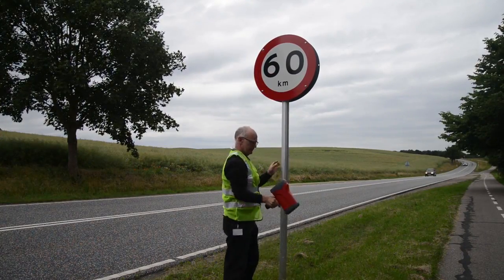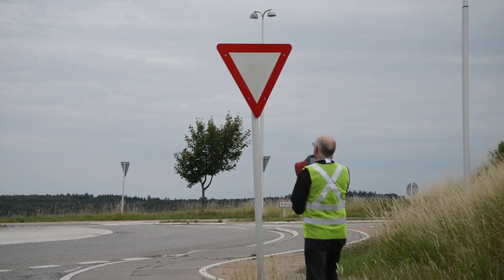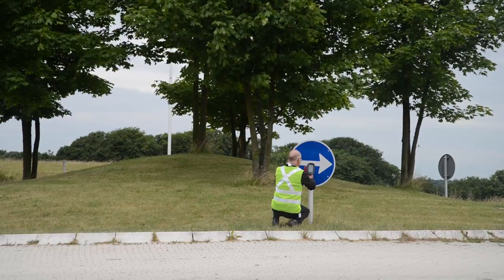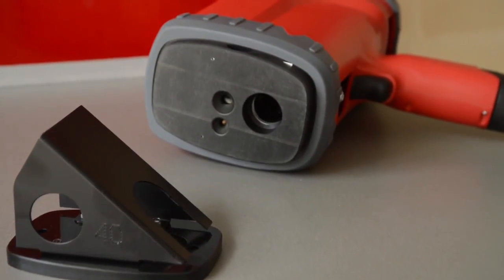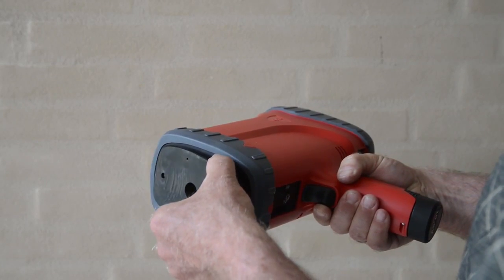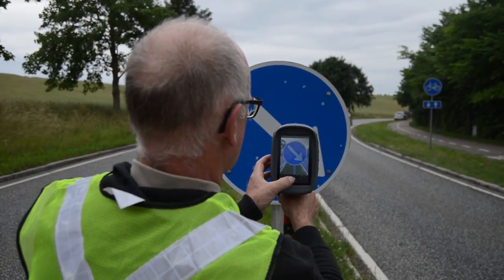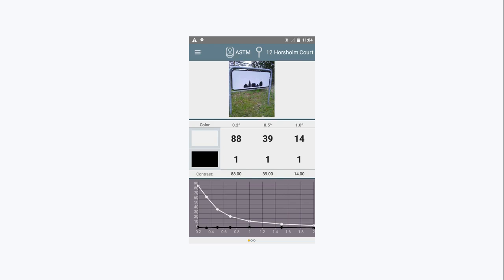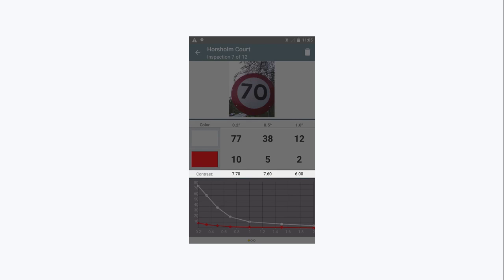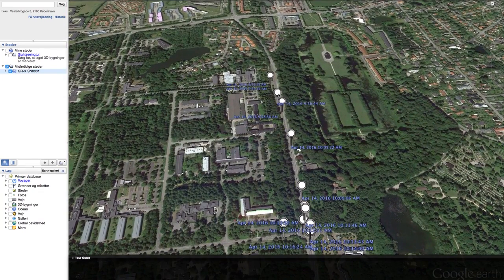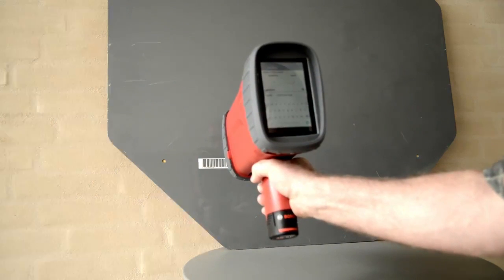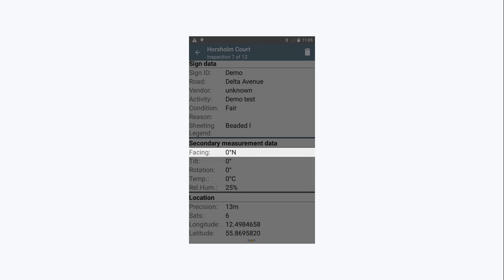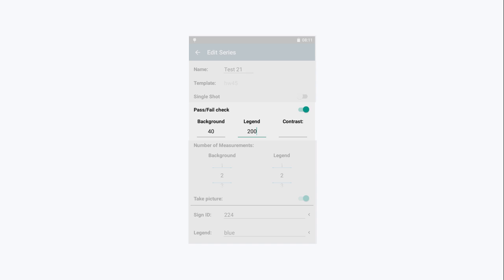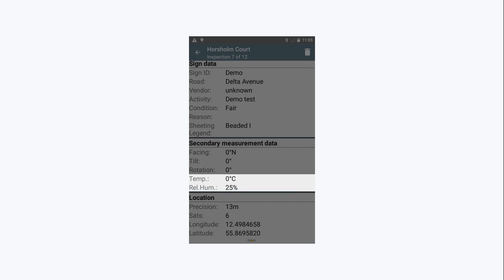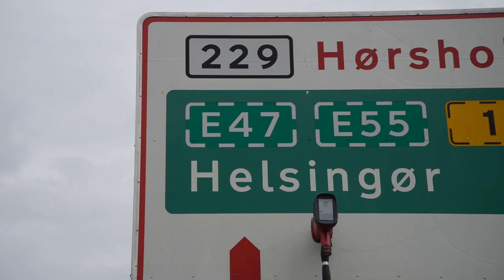GRX is built over the latest developments in sensor and digital camera technology, offering a range of valuable features, some of them not seen before in a retroreflectometer, like measurements of up to 7 observation angles simultaneously, measures 7 entrance angles by changing the front adapter, taking photo of the measured sign, automatic sign color recognition, contrast calculation of background and legend colors, built-in GPS for location identification, built-in barcode and QR code scanner for asset management, instrument tilt and rotation, sign facing direction, manually entered pass and fail values for background, legend, and/or contrast measurement values, temperature and relative humidity measurement, and extension pole for measurement of elevated signs.